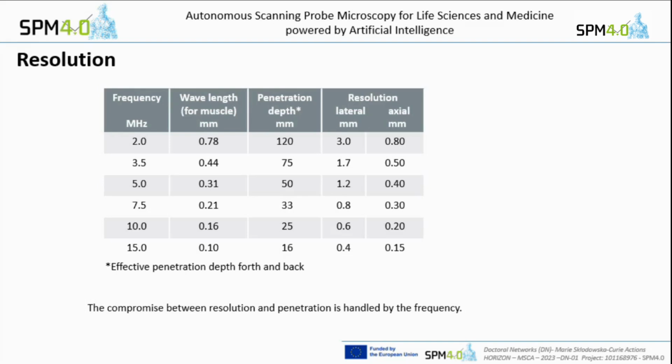For the application, if you go to the liver and so on, sometimes for a small person, we don't need 15 centimeters penetration depth and can adjust it a little bit. In the latest ultrasound devices, you can't set the frequency directly. You just say, okay, this is my highest penetration depth, and then the program automatically adjusts to the most proper.